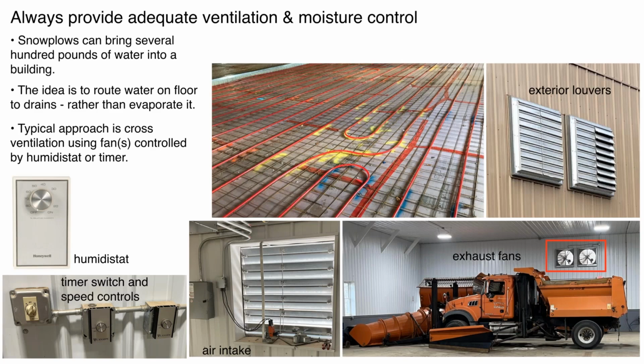Now, it is important with these garage facilities, actually with any building. Today, there are codes, there are ASHRAE standards on ventilation, and they could vary depending on what the building is. But in a garage type building, and I'm using, again, a highway garage, when a snowplow like what you see in the lower right comes in, that could have several hundred pounds of snow on it. And it's going to melt, it's going to drip down on that floor. The concept is that the first way we want to deal with that water, if possible, you want it to go down a drain. It takes a lot less energy to get rid of that water if we can drain it away rather than evaporate it.